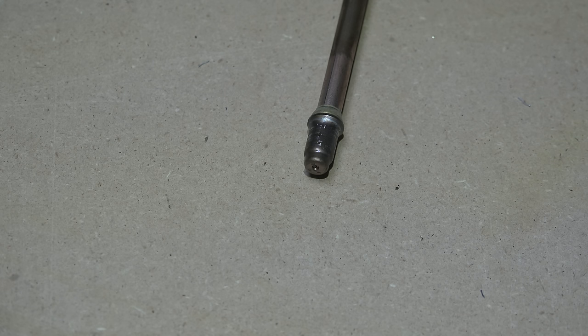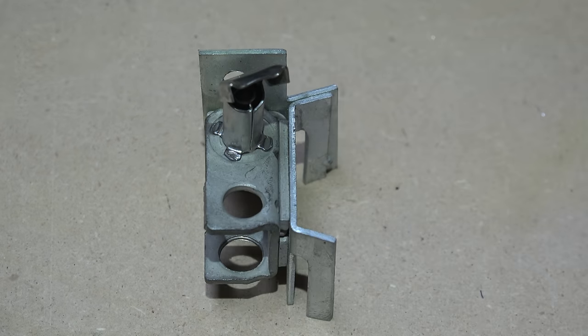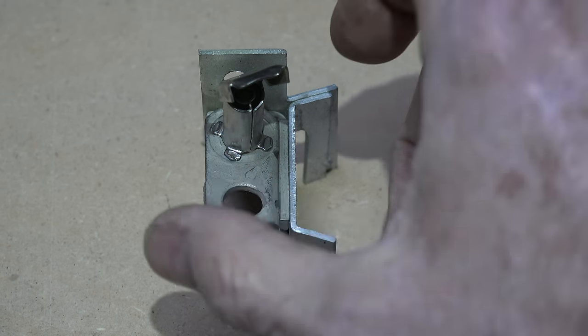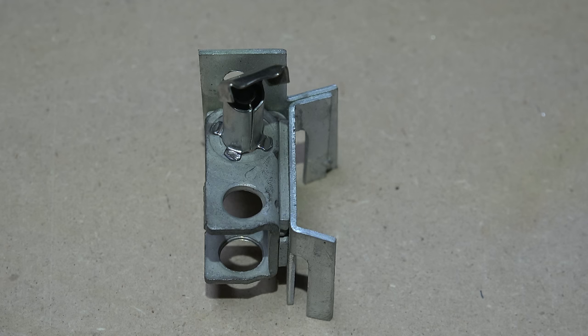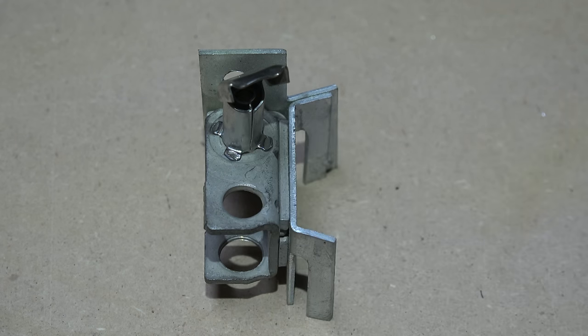That's pretty much how that pilot works. It's a little more complicated than you'd think - you'd think it's just a little doohickey that sits in there and gas comes out of it. It has a primary air addition and the secondary air comes around here. You know, I know they're not real popular anymore, but you still see them out there. The biggest problem with these things is this thing gets dirty in here - gets a bug in it or something like that - and it'll make it into a candle flame. It looks like a candle flame, it's not working. That's it on that one.